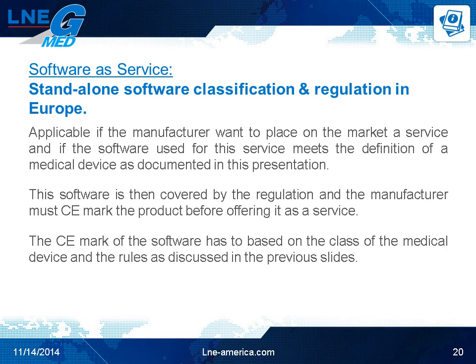If the manufacturer wants to place its software on the market as a service, and only if the software used for that service meets the definition of a medical device, the software is covered by the regulation and the manufacturer must CE mark the product before placing it on the market as a service. The CE mark of the software has to be based on the class of the medical device and the rules discussed in the previous slides.